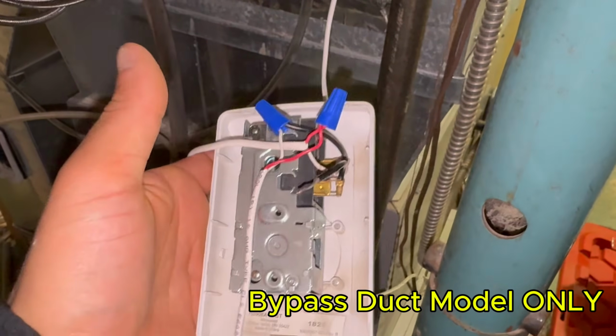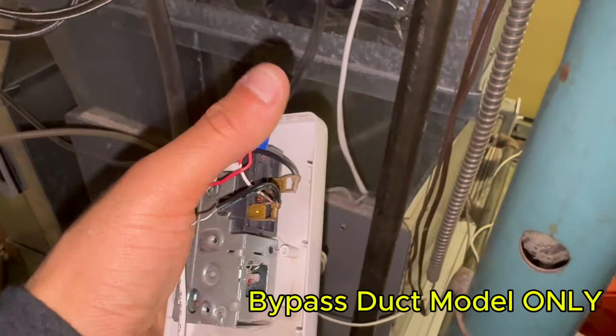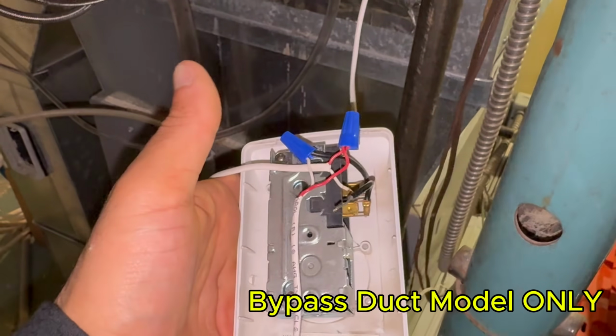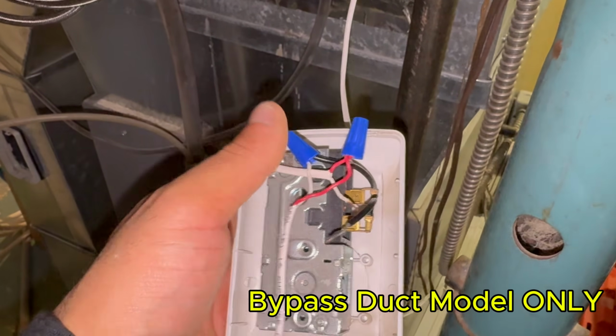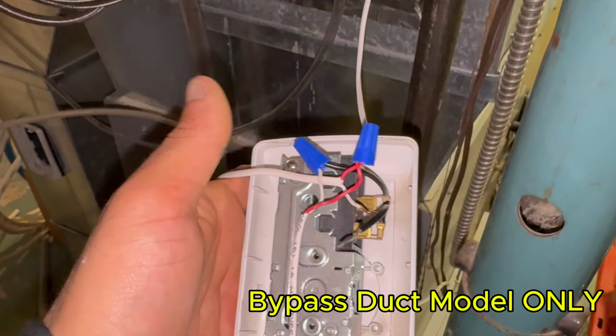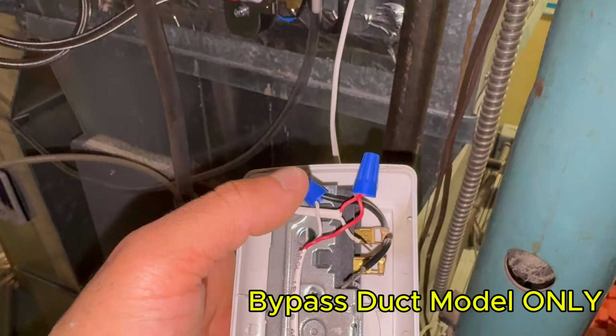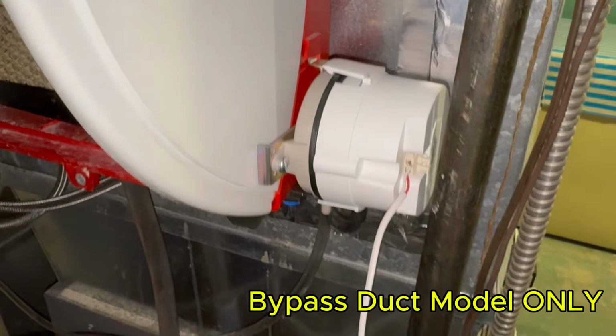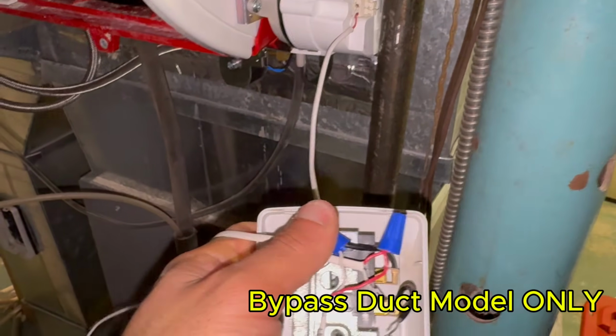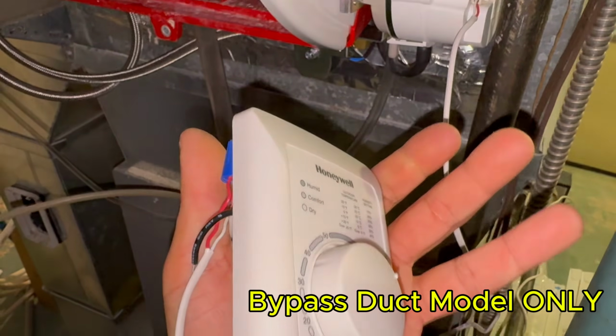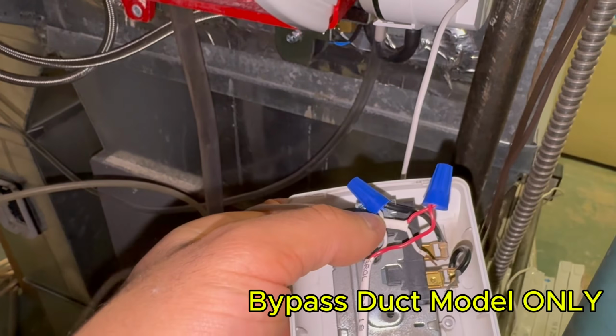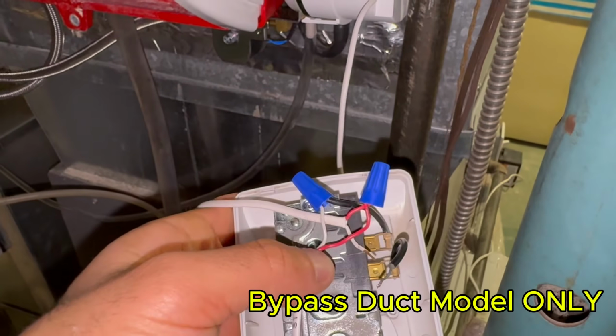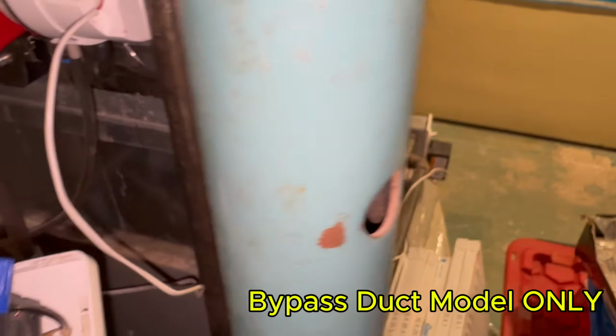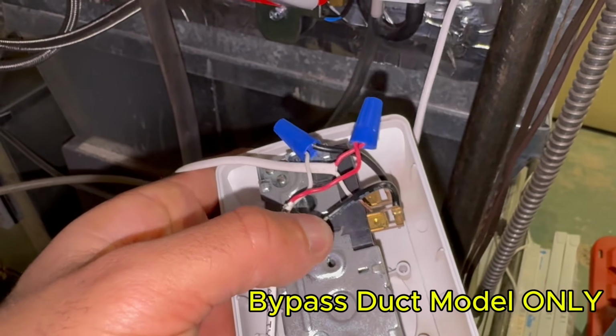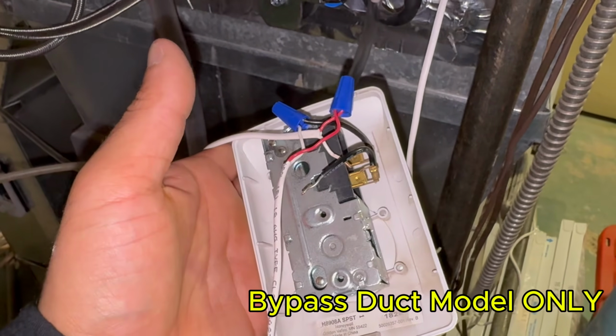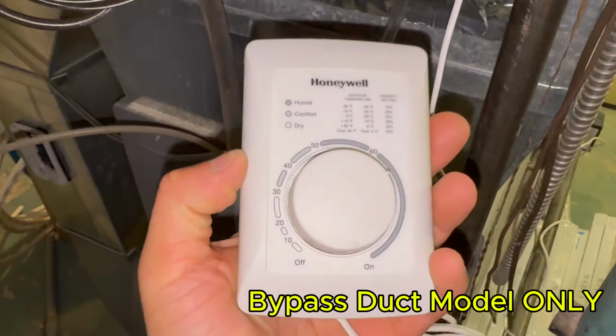Now that you've connected the 2 red wires, one coming from the pressure switch and the other from the transformer, you're now going to connect the 2 remaining white wires. You have 1 white wire coming from the control switch, and you're going to connect that to the 1 black wire on the humidistat. It doesn't matter which one. And then you'll have another white wire coming from the transformer, which you'll connect to the other black wire on your humidistat. Once you complete that, this is now active.